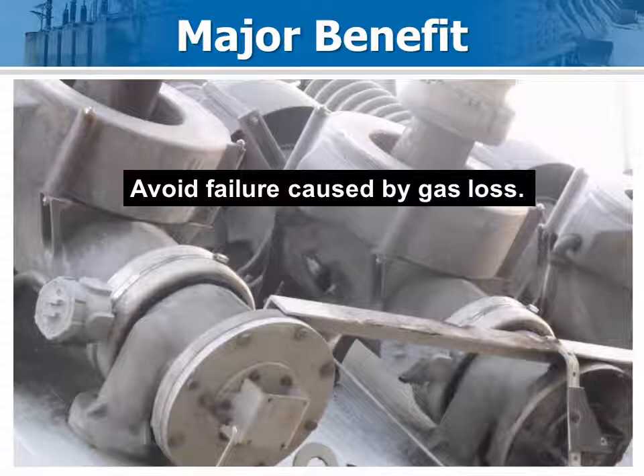From the system operator standpoint, the major benefit of the Optimizer 2 is the detection of incipient failures in circuit breakers. This lowers the risk and cost of maximizing equipment uptime. Avoiding the equipment failures that create sensational news is more important than ever. The interrupter here will cost the utility over $200,000 in unplanned expense.